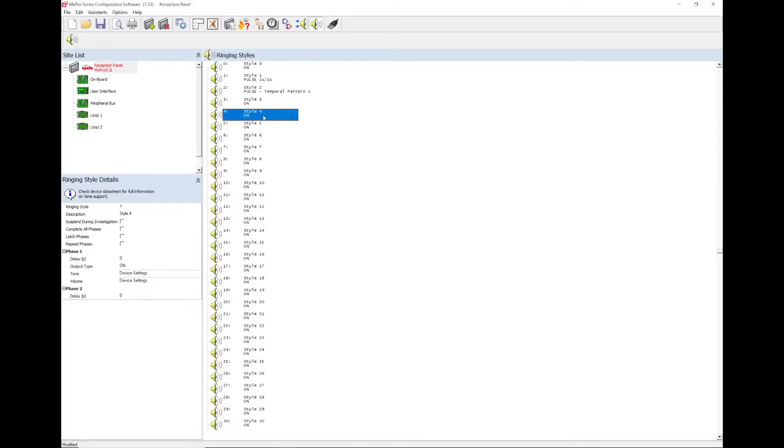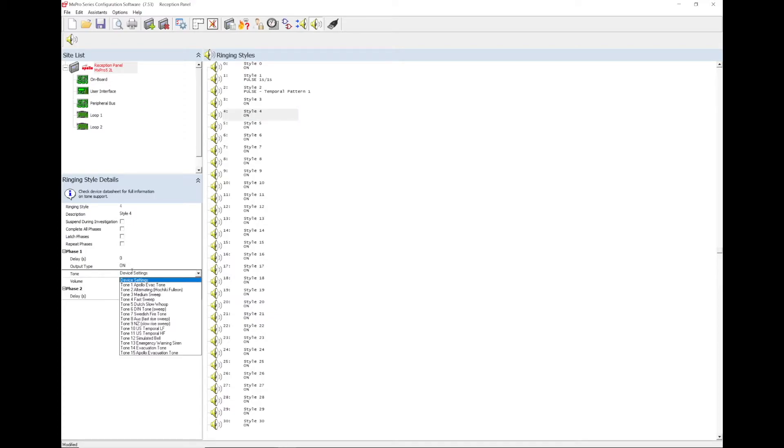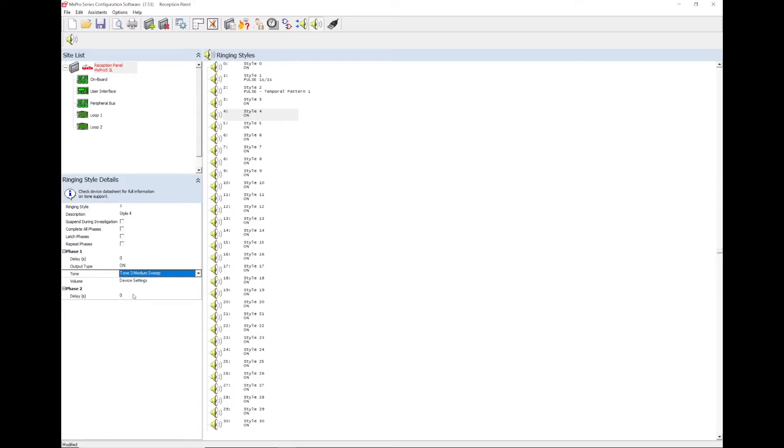Go to view edit ringing styles, then select an unused ringing style and look on the left hand side to the details. The output type could be changed to pulse or the tone could be changed depending on the type of sounders on site. The ringing style description can also be changed to a reference.